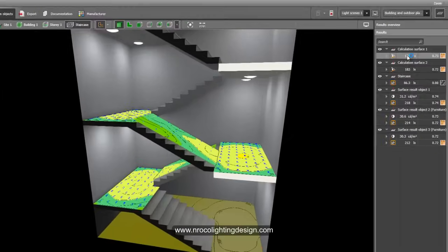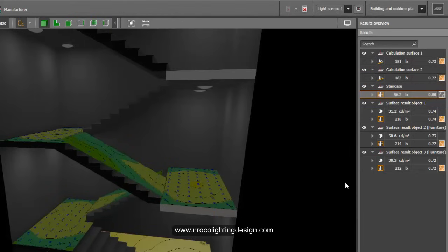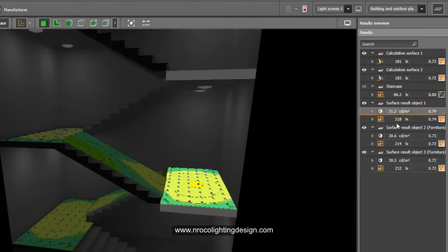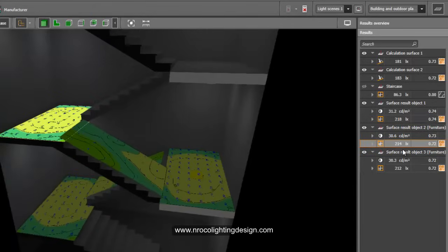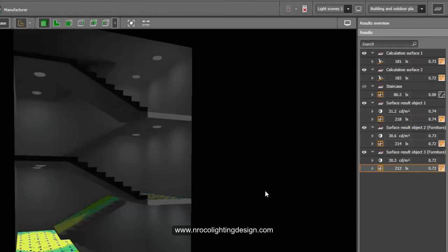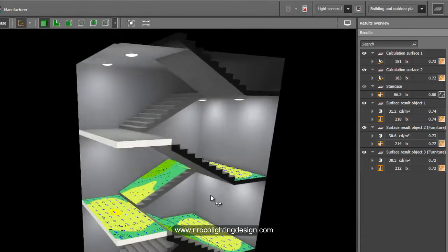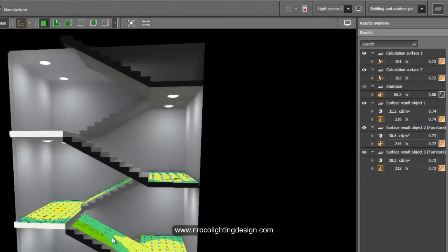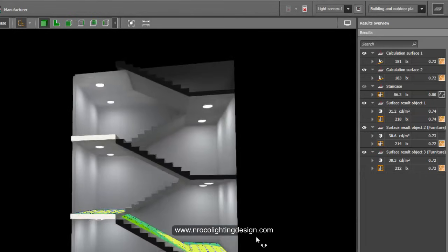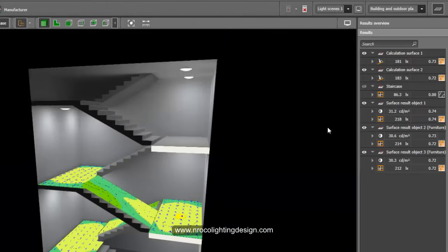The calculation is complete. One surface shows 181 lux, another 183 lux — these are on the inclined stair treads. The landing reads 218 and 214 lux — it's over-lit, but 200 lux is fine since there's a sensor for energy saving. Safety on staircases is very important, so 200 lux is acceptable. The inclined tread/horizontal surface shows 183 lux — fine.